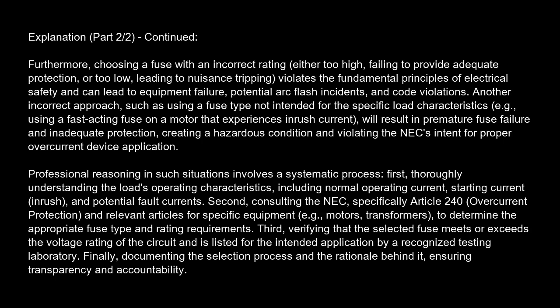Professional reasoning in such situations involves a systematic process. First, thoroughly understanding the load's operating characteristics, including normal operating current, starting current inrush, and potential fault currents. Second, consulting the NEC, specifically Article 240 overcurrent protection, and relevant articles for specific equipment, e.g., motors, transformers, to determine the appropriate fuse type and rating requirements. Third, verifying that the selected fuse meets or exceeds the voltage rating of the circuit and is listed for the intended application by a recognized testing laboratory. Finally, documenting the selection process and the rationale behind it, ensuring transparency and accountability.